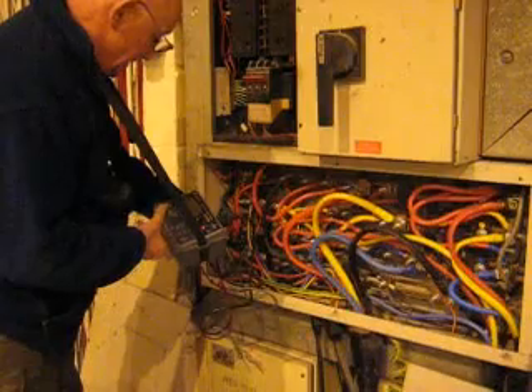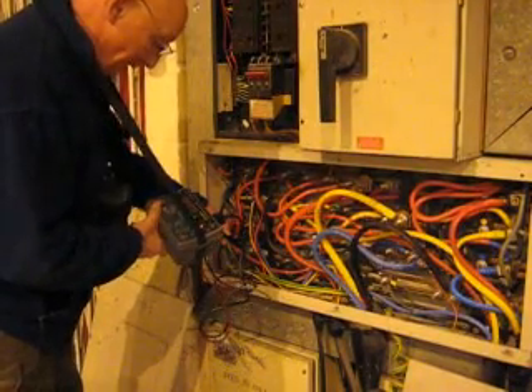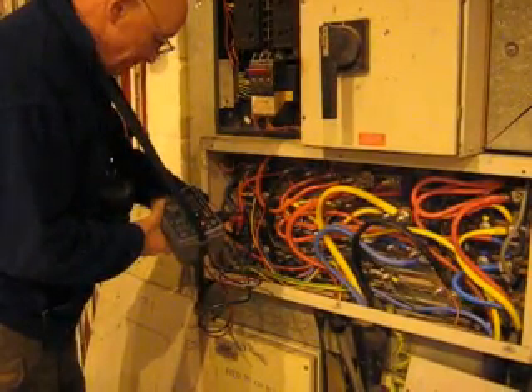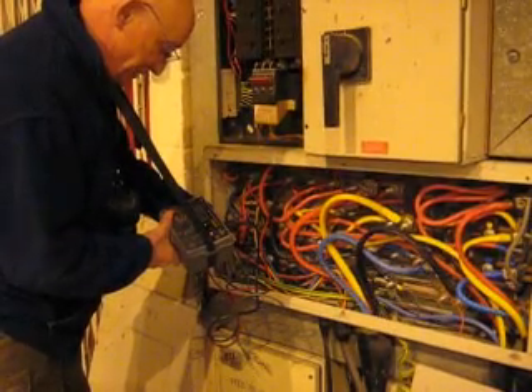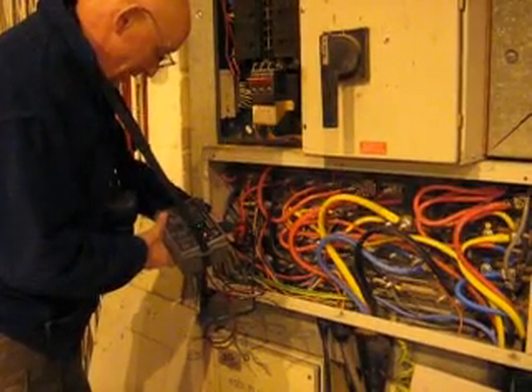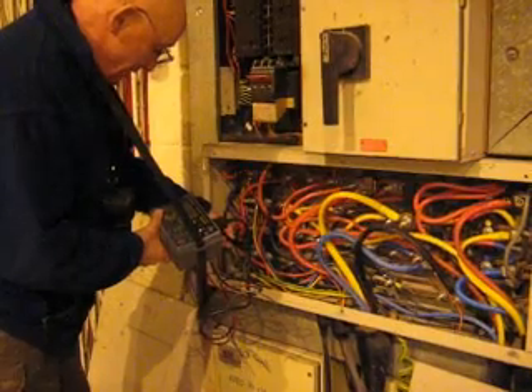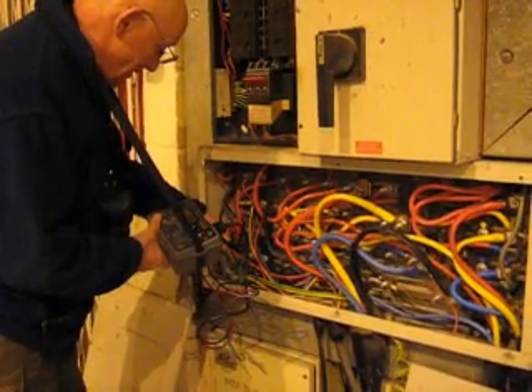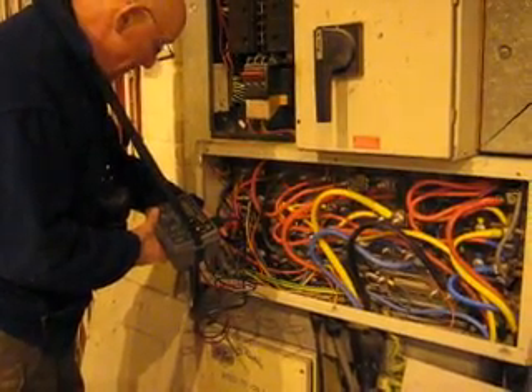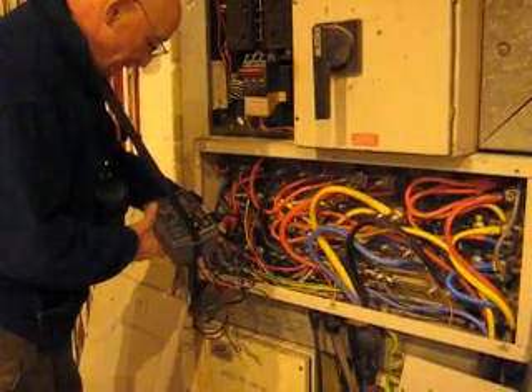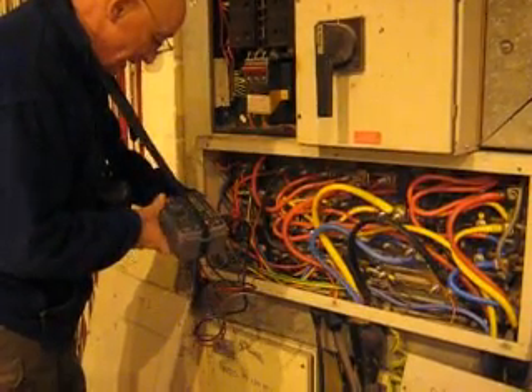Right, this is a test of phase earth loop impedance, and the impedance that I've just measured at this busbar chamber is 0.08. So at 240 volts, 240 divided by 0.08 gives 3 kA. Doubling it up because it's three phase, that's 6 kA.